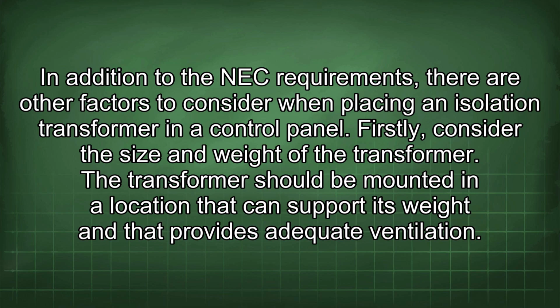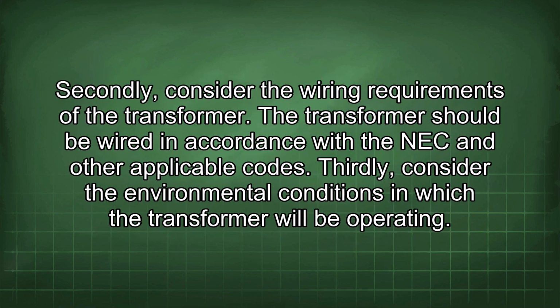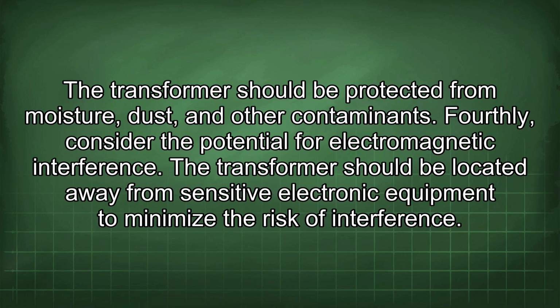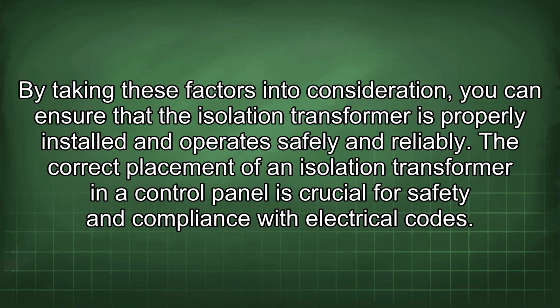The transformer should be mounted in a location that can support its weight and that provides adequate ventilation. Secondly, consider the wiring requirements of the transformer. The transformer should be wired in accordance with the NEC and other applicable codes. Thirdly, consider the environmental conditions in which the transformer will be operating. The transformer should be protected from moisture, dust, and other contaminants. Fourthly, consider the potential for electromagnetic interference. The transformer should be located away from sensitive electronic equipment to minimize the risk of interference. By taking these factors into consideration, you can ensure that the isolation transformer is properly installed and operates safely and reliably.